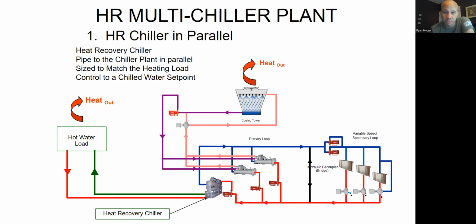So for example, let's just make up some numbers. Let's say this guy is a 500-ton chiller. This guy's probably a 500-ton chiller because nobody likes 2 different size chillers. They like to put 2 identical ones in. That way, if you ever need to grab a part off of one to get the other one up and running, you can do that. And it makes everything really balanced if you switch between the two. It's very rare that you would see one that's 800 tons and one that's 200 tons to get your 1,000 tons. So I have 500 and 500.